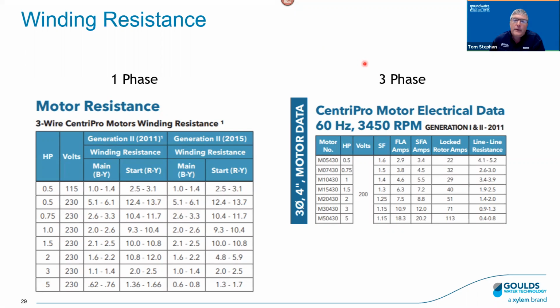And just for the heck of it, let's take a look at 3-phase, because sometimes there's some confusion there. If you do have a 3-phase motor, this happens to be just a little slice here. But once you look up your motor, you're going to see there's only one set of values, a min and a max, but you've got 3 leads on your 3-phase motor. It basically says that they should all be the same. So 3 leads, they're all the same: 1 to 2, 2 to 3, 1 to 3.